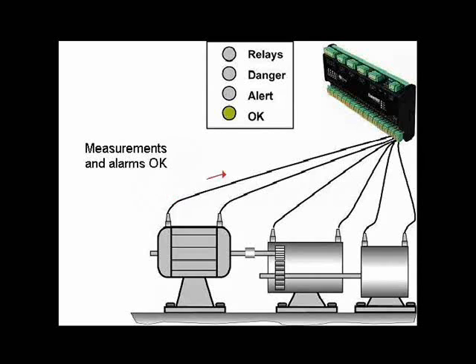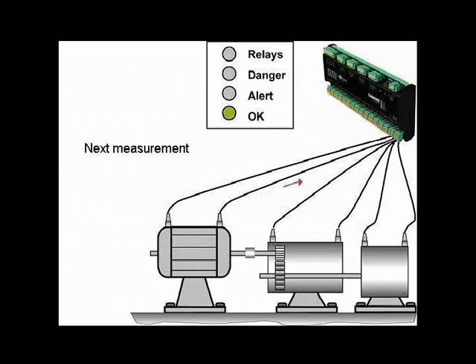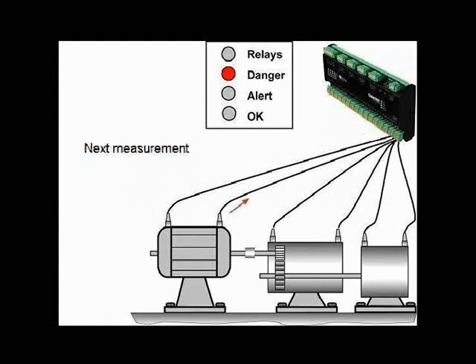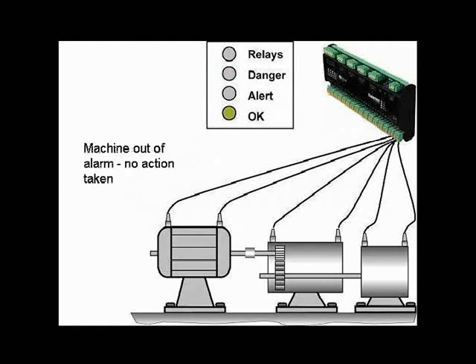Relays can be configured to activate audible alarms, warning lights, and even machine shutdowns when a particular alarm state is triggered. You can now specify how long an alarm state must persist before a relay is activated. A time delay period can be applied to any relay so that if a machine comes out of its alarm state during this time, the relay will not activate. This will help ensure that your monitoring system does not trigger a machine shutdown or alarm alert because of a single abnormal measurement.